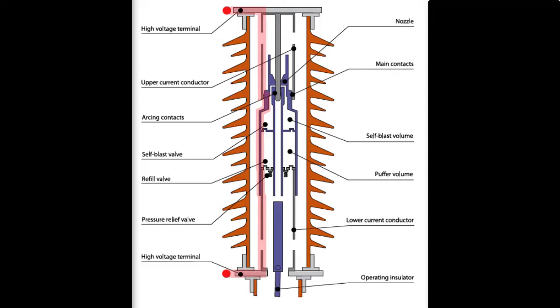Again, here we have the main stationary contacts and the moving contacts. During a breaking operation, the moving contacts move again, but the ablation causes the section here to fail, giving our pressurized heated gas an exit to move quickly through the gas nozzle like previously. The difference between this and a normal puffer operation being that here the gas moves much more quickly through the nozzle due to the extra energy imparted to the gas from the ablating section.